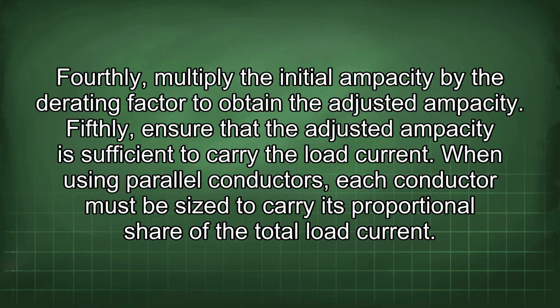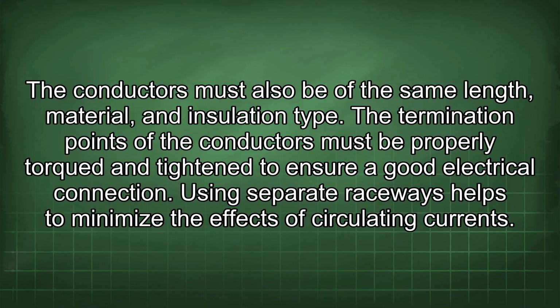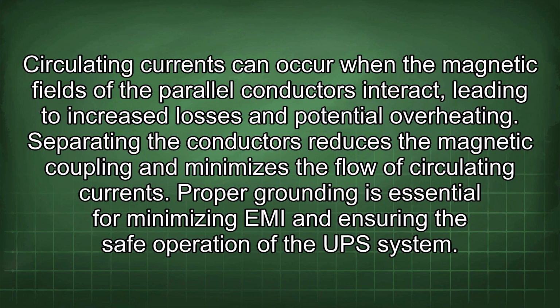When using parallel conductors, each conductor must be sized to carry its proportional share of the total load current. The conductors must also be of the same length, material, and insulation type. The termination points of the conductors must be properly torqued and tightened to ensure a good electrical connection. Using separate raceways helps to minimize the effects of circulating current. Circulating currents can occur when the magnetic fields of the parallel conductors interact, leading to increased losses and potential overheating. Separating the conductors reduces the magnetic coupling and minimizes the flow of circulating current.